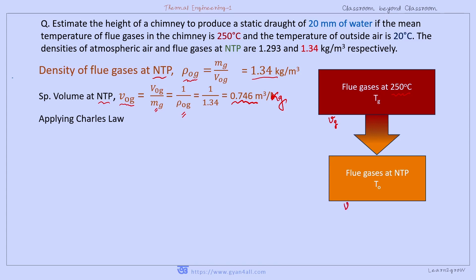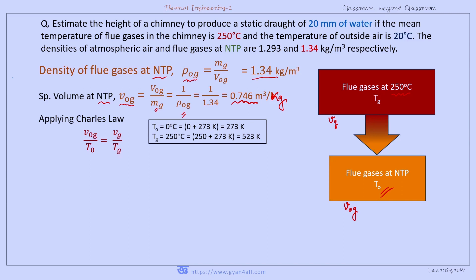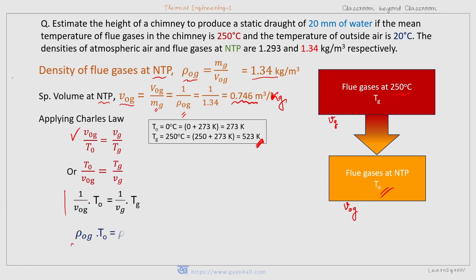The specific volume of the flue gas is v_G, and when reduced to NTP it becomes v₀_G. Applying Charles's Law: v₀_G/T₀ = v_G/T_G. The temperature of the flue gas T_G is 523 K. Rewriting: T₀/v₀_G = T_G/v_G, which gives ρ₀_G·T₀ = ρ_G·T_G. T₀ is 273 K and T_G is 523 K, so we can now find ρ_G.